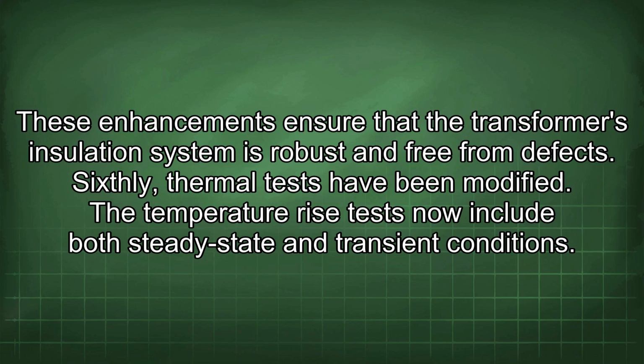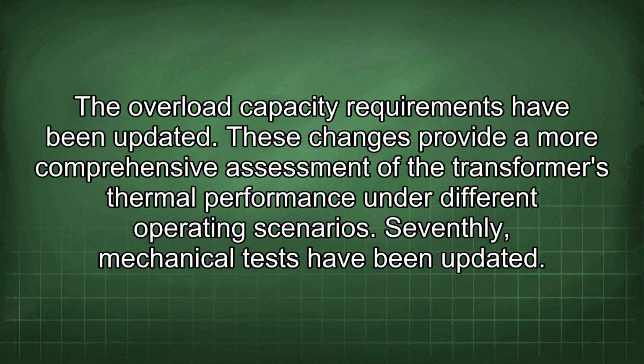Sixthly, thermal tests have been modified. The temperature rise tests now include both steady state and transient conditions. The overload capacity requirements have been updated. These changes provide a more comprehensive assessment of the transformer's thermal performance under different operating scenarios.